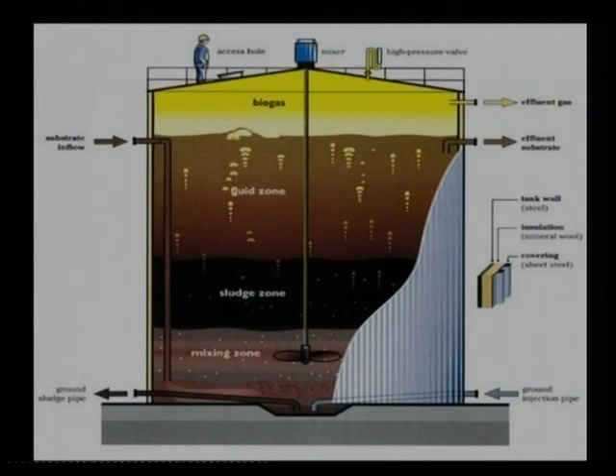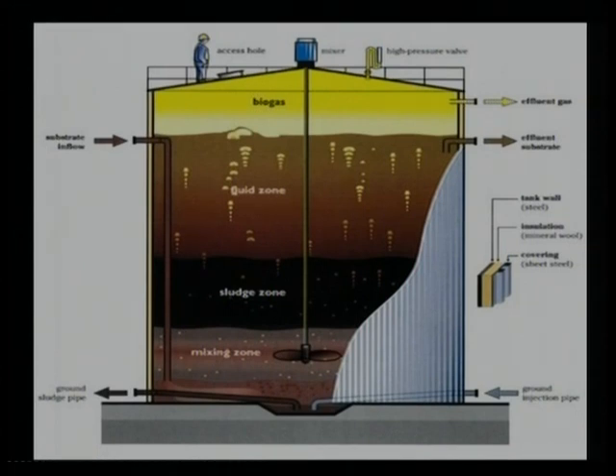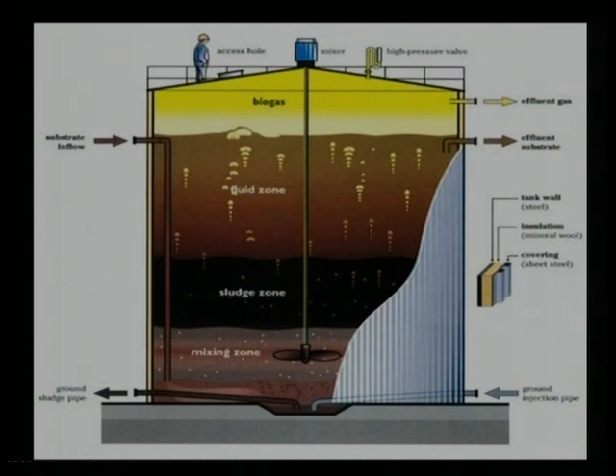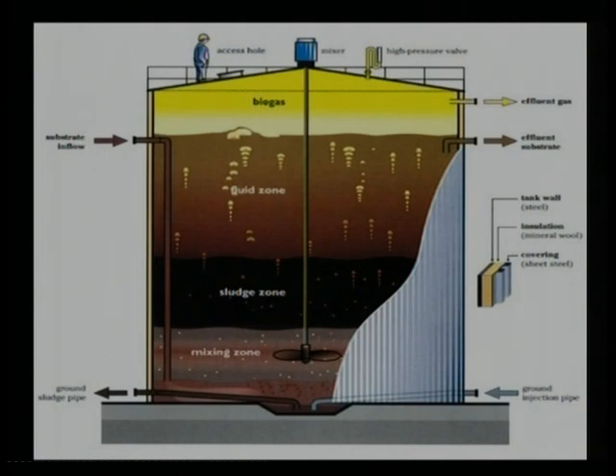In this schematic diagram, at the base there is a mixing zone where solid sludge is added. In the center is the sludge zone where thermophilic and anaerobic organisms carry out acidogenesis, acetogenesis, and hydrolysis. The liquid decreases, sludge thickens, and methane gas is liberated. The yellow portion at the top shows biogas collection. Temperature and pH are very significant in this digester. Both single-chamber and double-chamber anaerobic sludge digesters are used in wastewater treatment plants.